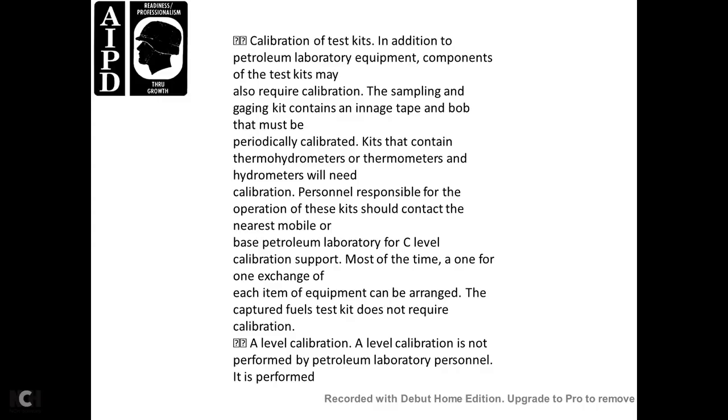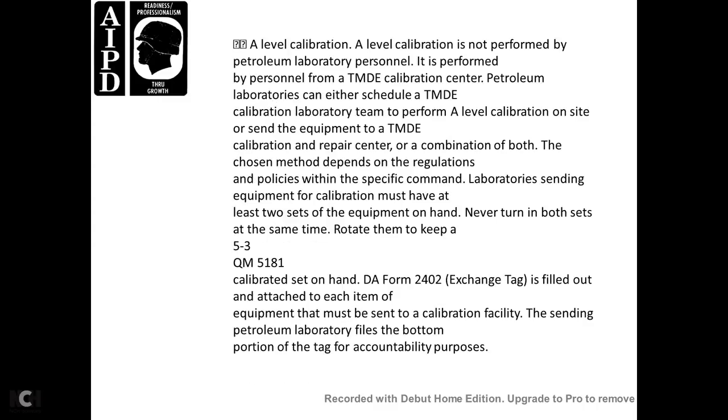A-level calibration is not performed by the petroleum laboratory personnel. It is performed by personnel with the TMDE calibration center. The petroleum laboratories can either schedule a TMDE calibration laboratory team to perform A-level calibration on site, send the equipment to the TMDE calibration repair center, or use a combination of both. Choosing the method depends on the regulation and policy.